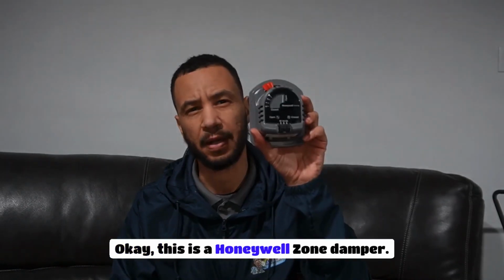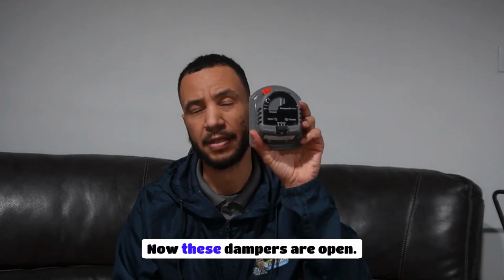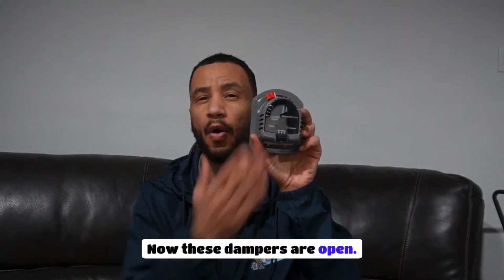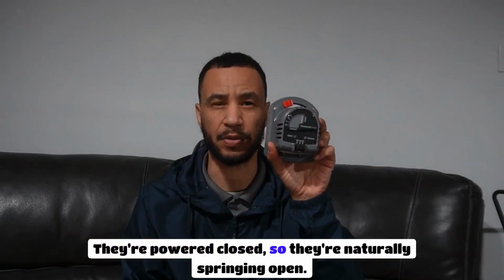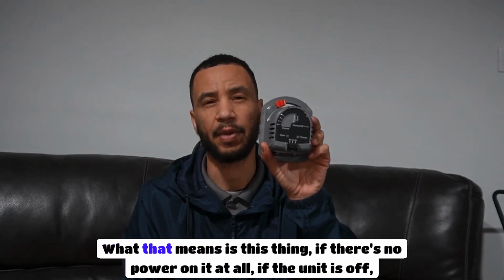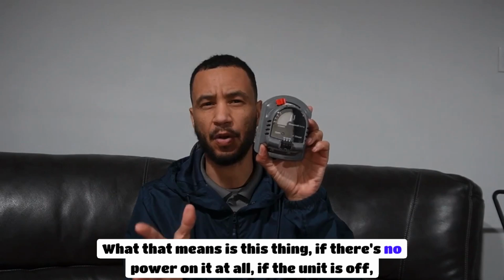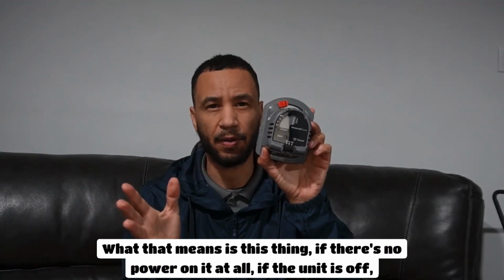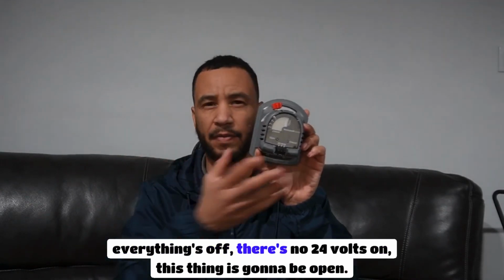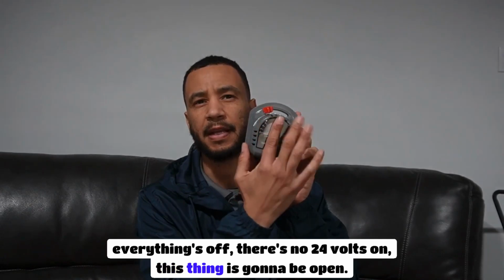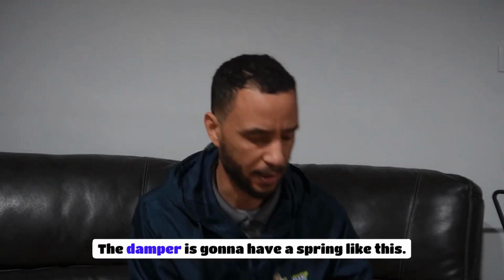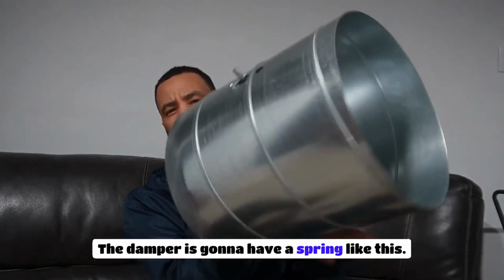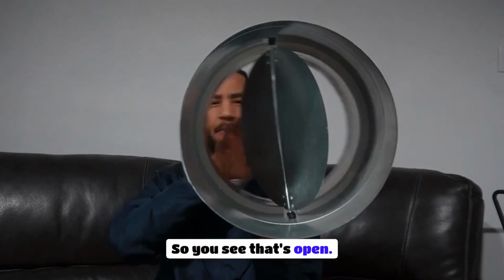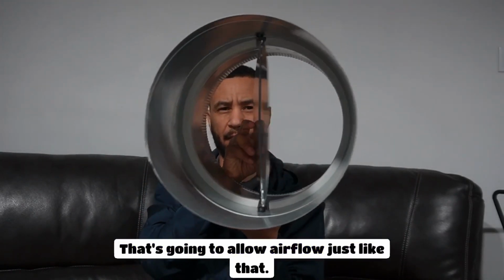Okay, this is a Honeywell zone damper. Now these dampers are open. They're powered closed, so they're naturally springing open. What that means is, if there's no power on it at all, if the unit is off, everything's off, there's no 24 volts on, this thing is going to be open. The damper is going to have a spring like this. So you see that's open, that's going to allow airflow just like that.